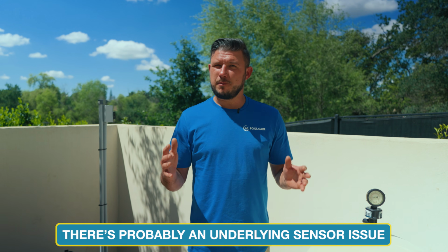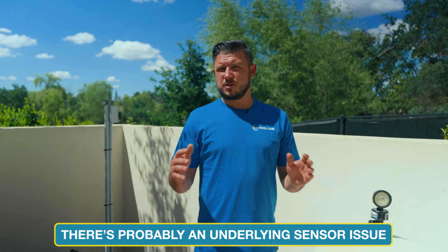You might have a case where your heater turns on and starts heating water, but it doesn't reach the set desired temperature. In that case, there's probably an issue with one of the sensors. The sensor went bad and it thinks the water has reached 104 or 102 or whatever you've set, but it's misreading the temperature.